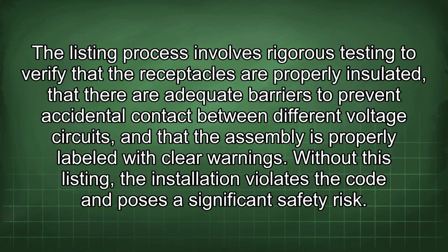The listing process involves rigorous testing to verify that the receptacles are properly insulated, that there are adequate barriers to prevent accidental contact between different voltage circuits, and that the assembly is properly labeled with clear warnings. Without this listing, the installation violates the code and poses a significant safety risk.